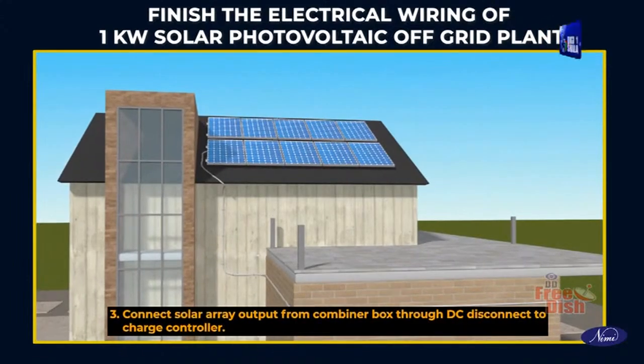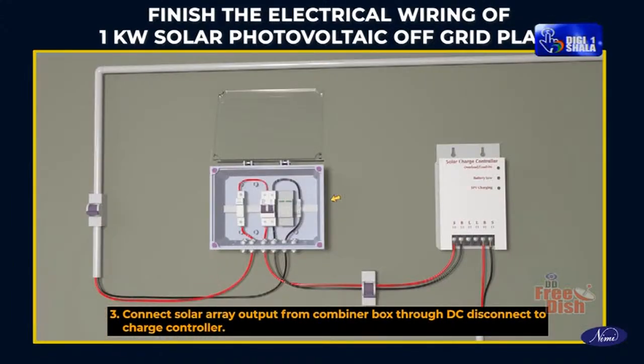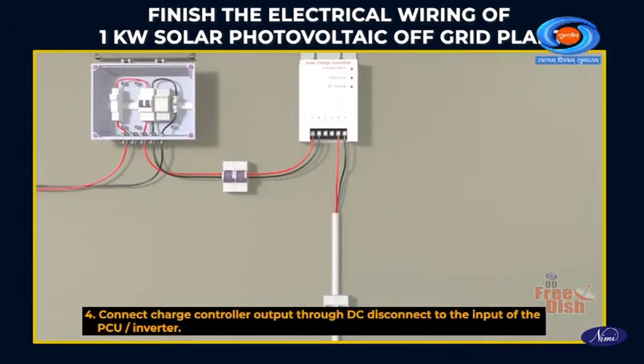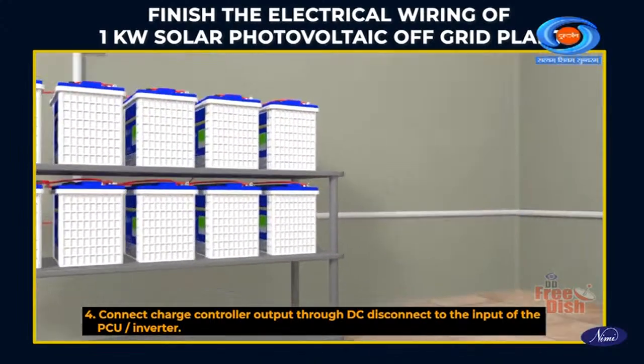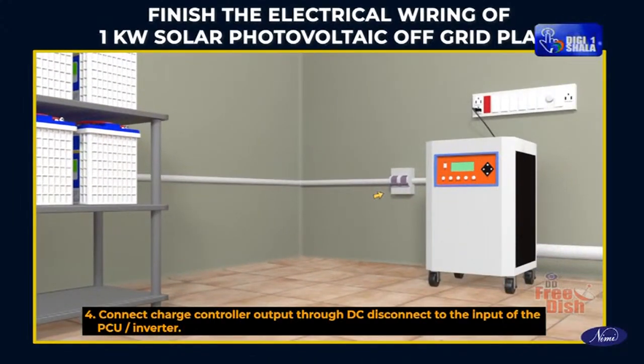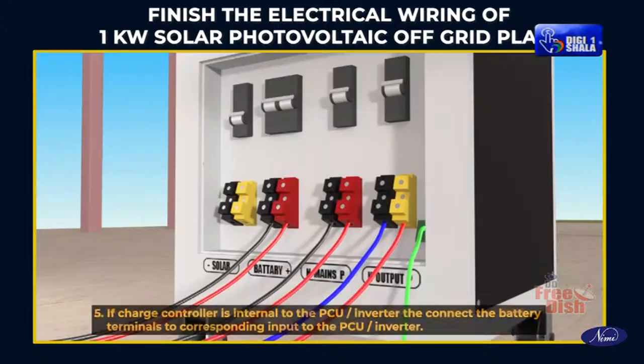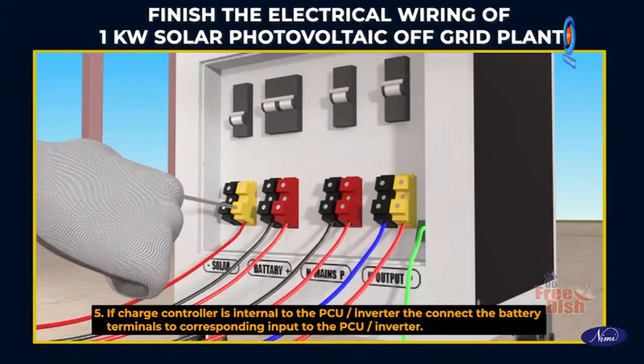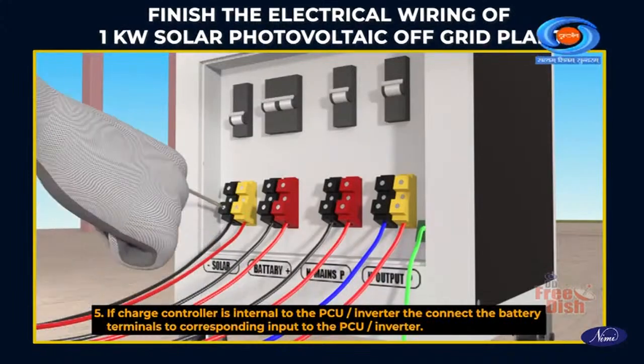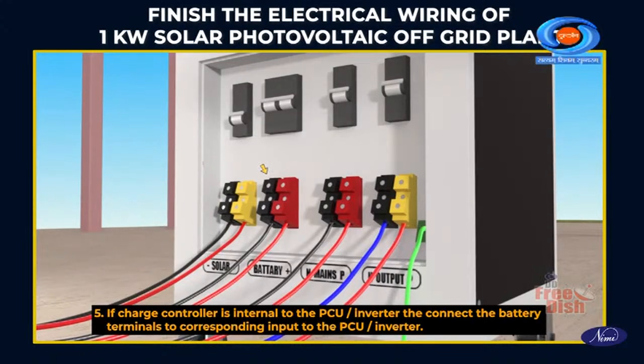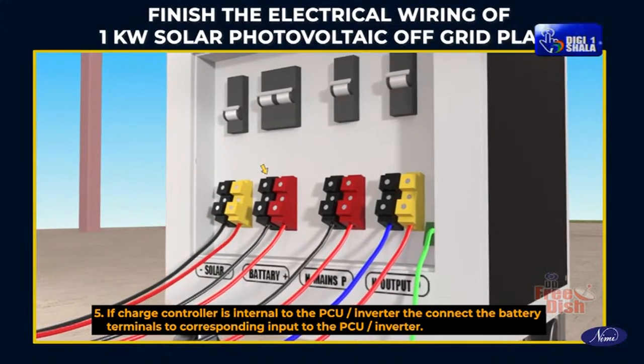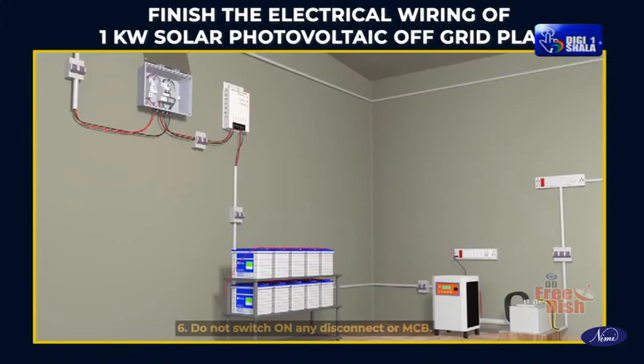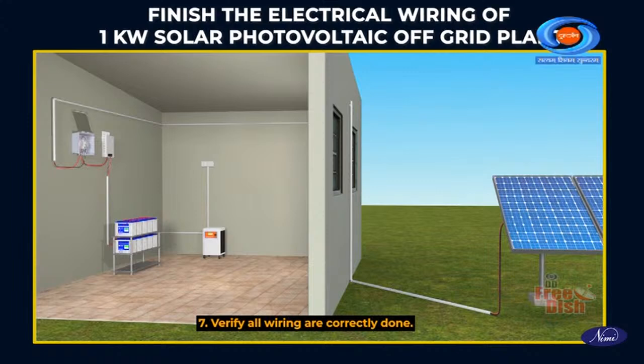Connect solar array output from combiner box through DC disconnect to charge controller. Connect charge controller output through DC disconnect to the input of the PCU or inverter. If charge controller is internal to the PCU or inverter, connect the battery terminals to corresponding input to the PCU or inverter. Do not switch on any disconnect or MCB. Verify all wiring is correctly done.